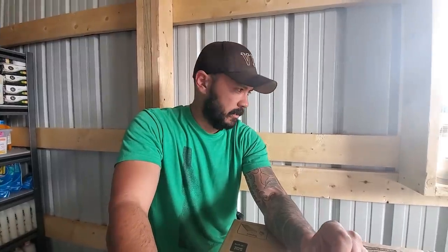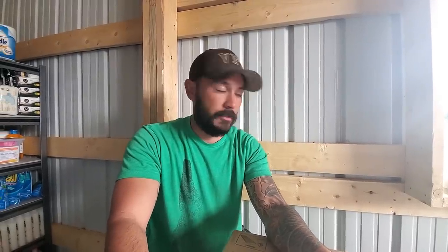So we had a minor setback in the work that we were doing today. We had a state inspector come by to take a look at our building and our setup, and everything was fine outside of the building, but with everything that we're getting done in here, we had to make some modifications to our plan. We don't plan on putting up any kind of sheeting in here. Everything's going to be out and exposed. So with the wiring we're putting in, they want to make sure that it is completely encased, concealed, and out of view to minimize any kind of risk of injury or somebody being electrocuted.